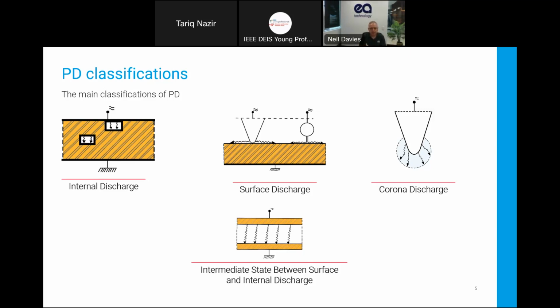If we see that in an open terminal busbar switchyard, then again, not often a problem. It may just be the bus roller that is sitting slightly off and everything not 100% bonded. It causes us more interference and it causes us a problem. If that's on a contact inside maybe an 11 kV cable termination, plug-in termination, then that would be a problem that we would need to address.